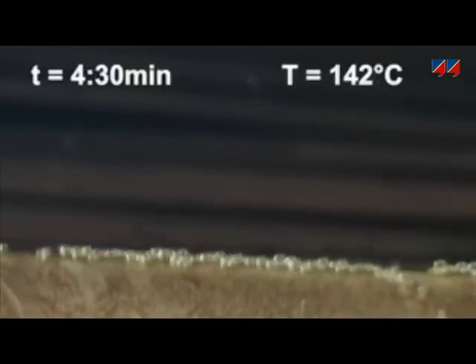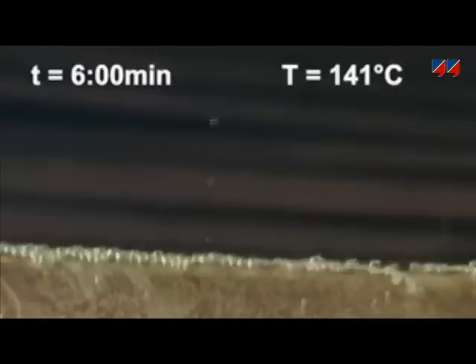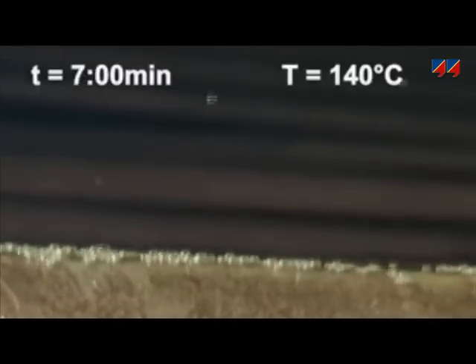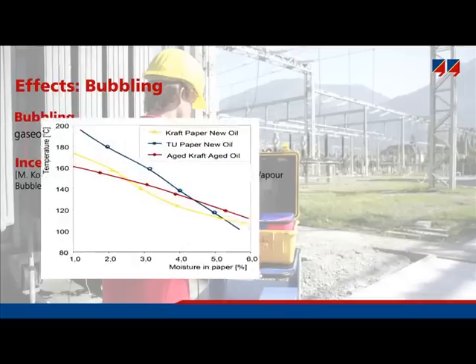Ten layers of paper having four percent moisture content are wrapped around a heated conductor. On the right-hand side of the window, you can see the temperature on the surface of this conductor, below the paper layers. Bubbling starts at 140 degrees centigrade. The bubbles decrease the dielectric strength of the oil, and a breakdown or partial discharges may occur. The bubble inception temperature is dependent on the moisture content, as depicted in the graph showing bubble inception temperature over moisture content of the paper.